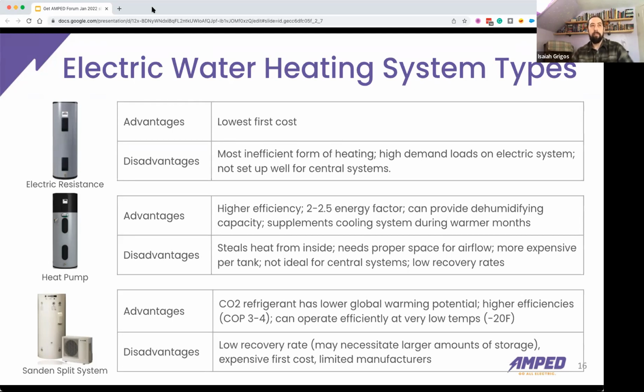We've seen these both in-unit, installed in an apartment, and as a more centralized system. You can't stick 30 of these in a basement and expect them to work properly, because they'll cool the air too much and end up being inefficient. But we have seen a setup where they're located in mechanical closets off of corridors, using the corridor air that they require. It's nice because it's out of the apartment.